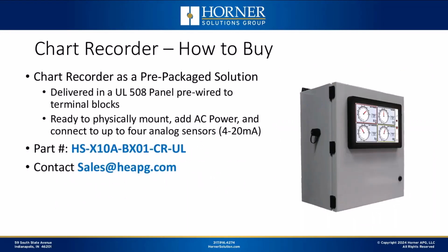Now, in terms of how to buy it, there are 2 different forms in which you can purchase the chart recorder solution. You can purchase it as a pre-packaged solution. In other words, pre-installed in a UL508 control panel, where everything is pre-wired. So all you have to do is physically mount the enclosure, add AC power to the appropriate field terminals inside the box, connect up to 4 sensors to the appropriate terminals inside the box, power the unit up, set a few settings from the touchscreen, and you're up and going right away.